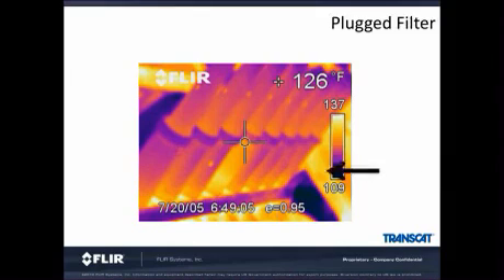In this example, we can see that one filter stands out from the others. We had talked earlier about looking for uniformity, what doesn't stick out. In this case, one of the filters is about 10 degrees warmer. The increased temperature was caused because the filter was clogged. This is not a target normally scanned by a thermal camera, but obviously one can benefit from it. And the reliability engineer or the maintenance person was able to determine which one of these filters was actually having the problem.